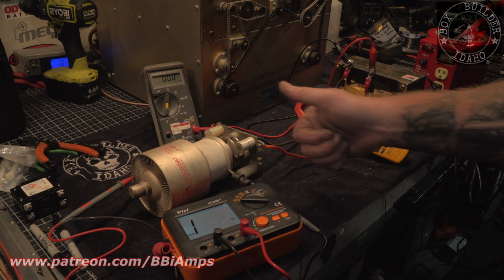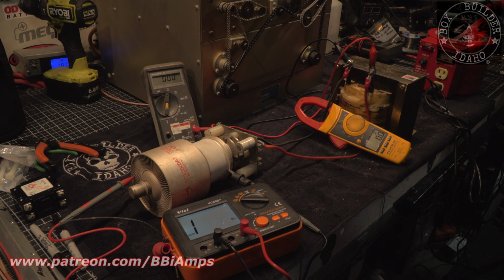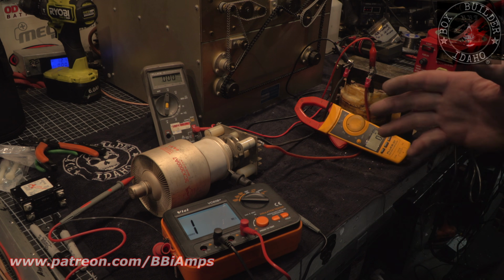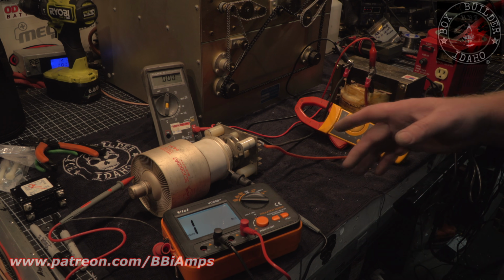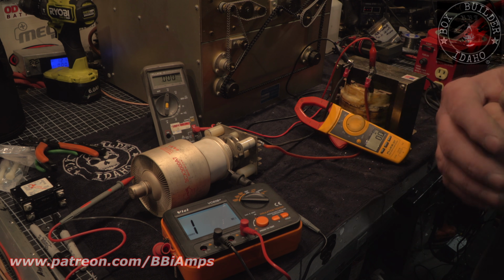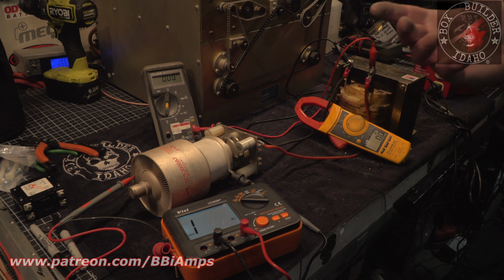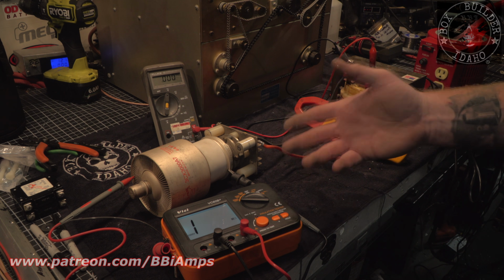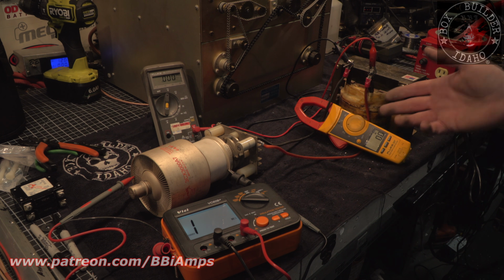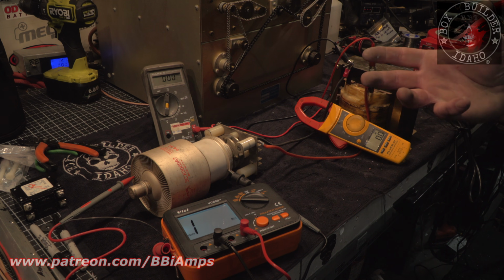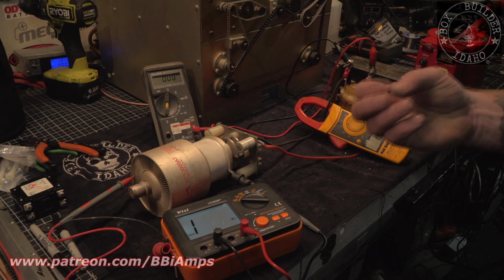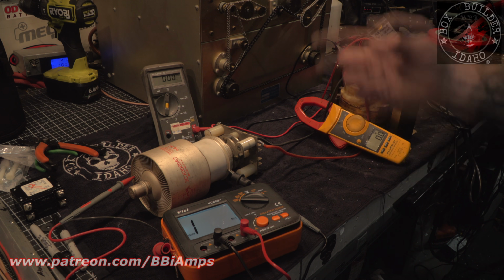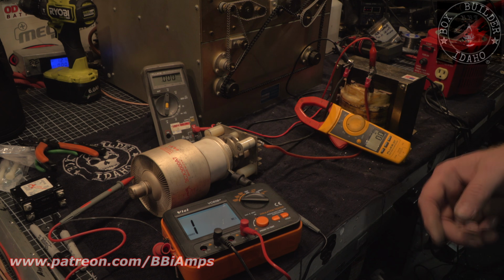Yeah, that's a win, it's acting like it's new. I was very concerned. I'm not too worried about anything else right now with this tube, other than it didn't have a leak in it. This is like an air bottle test that I do with the 3500Z - you turn it on, let it light up, see if the internal structure of the tube disintegrates because there's no vacuum. Same principle here.